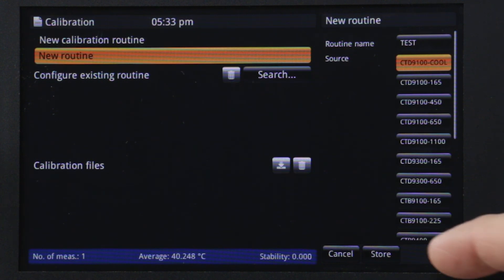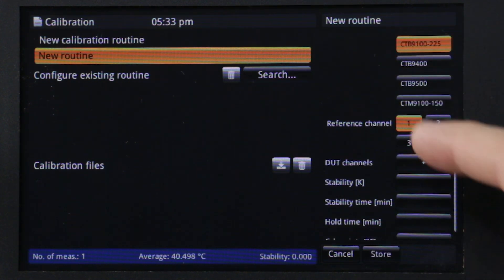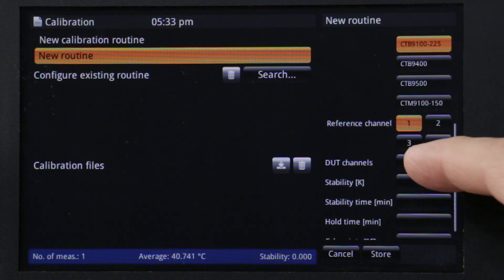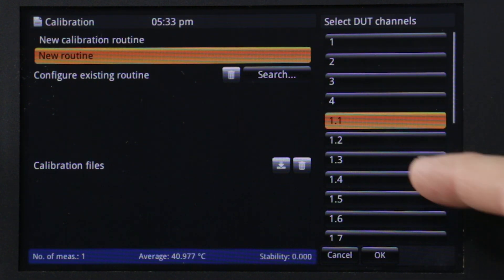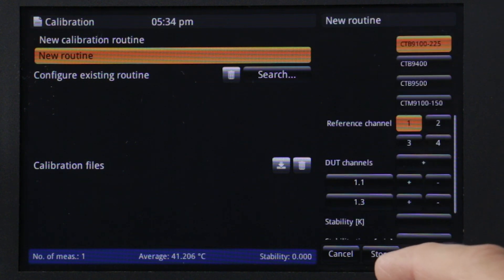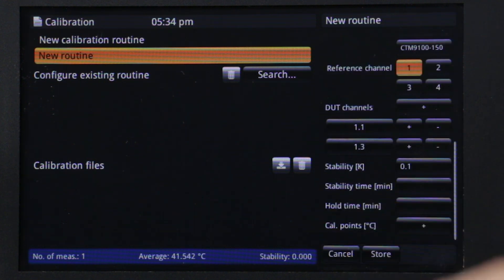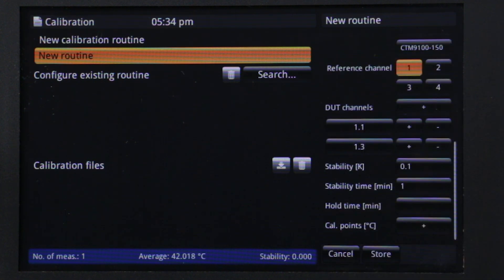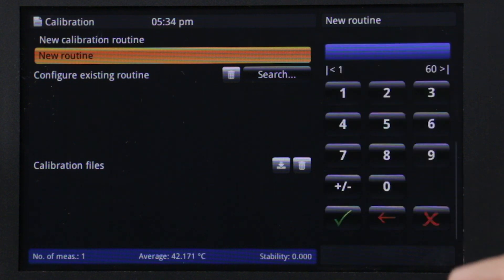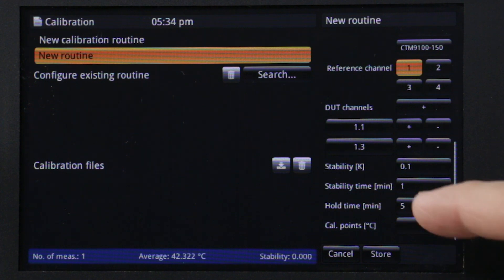Inputs in the calibration routine define a specific bath or dry well, the reference thermometer channel, and the channels connected to each device under test through the multiplexer. Parameters also include the test stability, stability time, and hold time. And the temperature set points.